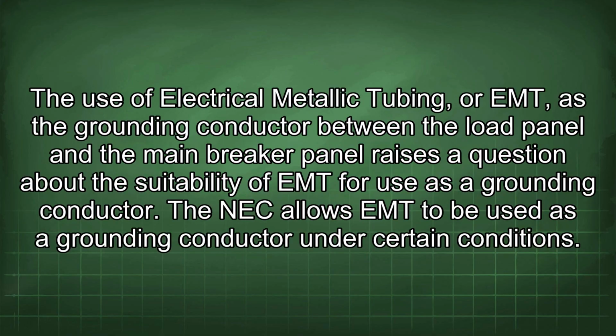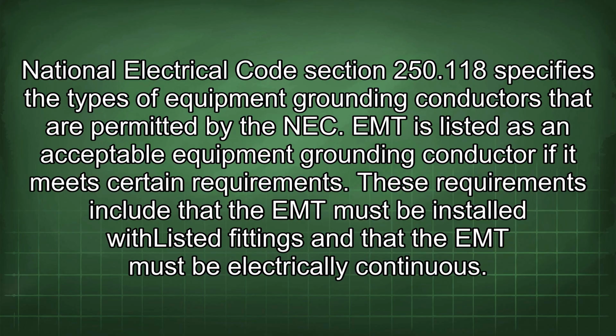The use of electrical metallic tubing, or EMT, as the grounding conductor between the load panel and the main breaker panel raises a question about the suitability of EMT for use as a grounding conductor. The NEC allows EMT to be used as a grounding conductor under certain conditions. National Electrical Code Section 250.118 specifies the types of equipment grounding conductors that are permitted by the NEC. EMT is listed as an acceptable equipment grounding conductor if it meets certain requirements. These requirements include that the EMT must be installed with listed fittings and that the EMT must be electrically continuous.